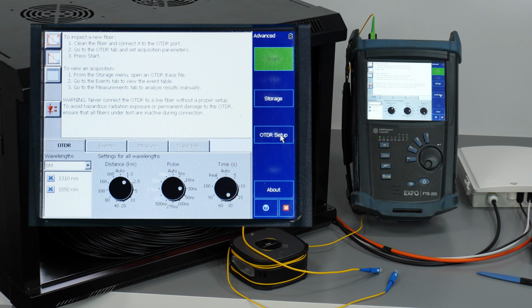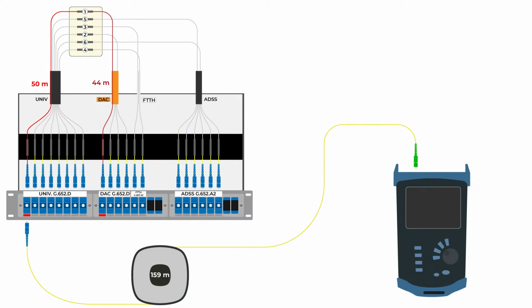The dead zone generated by such a pulse will not be an issue, as the weld is preceded by several tens of meters of fiber, regardless of the measurement direction. The averaging time was set to 30 seconds. The end of the measured line is an SC-UPC connector, which, polished straight, causes significant light reflection. This reflection can unnecessarily obscure the reflectogram. To limit the reflection at the end of the line, it was extended using a short SC-UPC, SC-APC patch cord. This fact has no significance for the accuracy of the measurements taken.